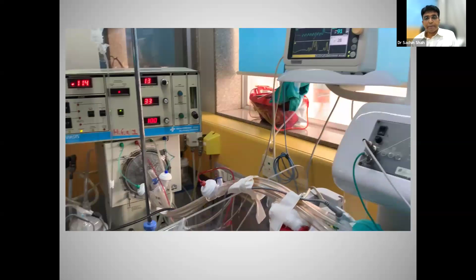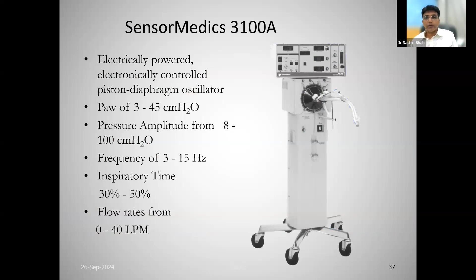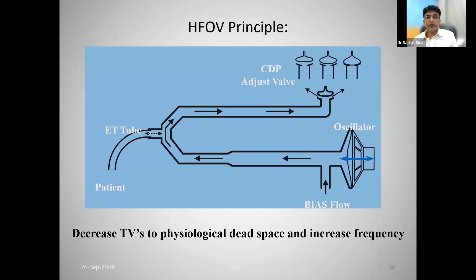I'm not going into the specifics of the different machines, but a frequency of 3 to 15, a pressure amplitude from 8 to 100, and an I time from 30 to 50 is what the machine can deliver. There is a valve here, and there is a piston. The piston moves, and along with the bias flow, the machine will deliver the mean airway pressure here. The tidal volume, as I told you, is very small in high frequency ventilator.